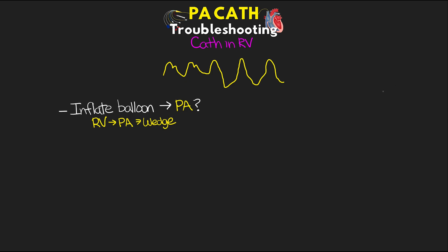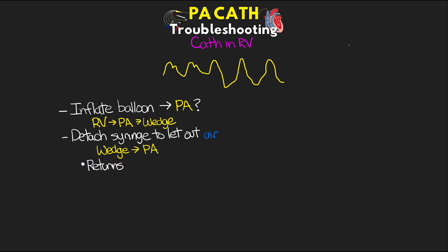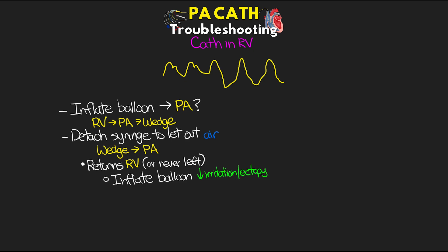Once that wedge is observed, we want to detach the syringe to remove the air, and we should see a return of the normal PA waveform. Now if it returns to RV, or we never actually left the RV, then we want to ensure that the balloon is inflated. This minimizes any irritation in the right ventricle — it basically pads the tip of the catheter and can help prevent some of the ectopy that can happen.